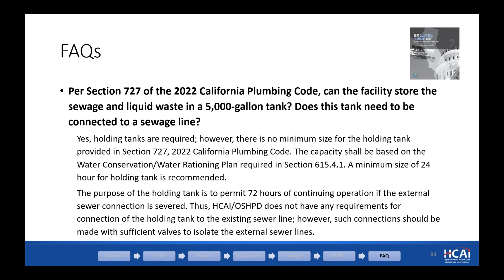Again, we are recommending a minimum size of 24 hours for the holding tank. The purpose of the holding tank is to support 72 hours of continued operation if the external sewer connection is damaged. And we do not have any requirements on connection of the holding tank to the existing sewer line. However, if connections are provided, make sure that they're made with sufficient valves to isolate the external sewage lines.